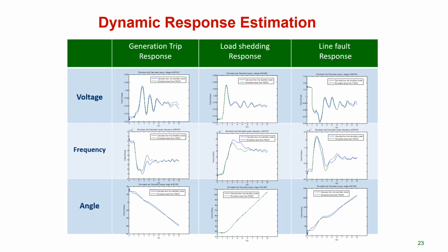You don't have to run the whole system. Let's say TVA wanted to run transient analysis faster than real time. You cannot do that running the whole EI, you're far from doing that. However, if you can have a very accurate equivalencing of the grid at that moment, you can have a very good, small, accurate model of the TVA system only, and then you have a capability to carry out analysis faster than real time.